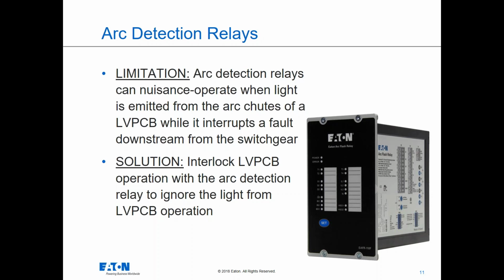The light detection system, while everyone is of the understanding that light detection is faster than a direct electrical method of measurement and then, you know, circling back to a circuit breaker to operate it, what cannot be expressed empirically is what the actual clearing time changes by utilizing these methods. That has to do with tested combinations of equipment. That has to do with light detection sensors being in non-repeatable places within equipment, and the fact that equipment varies from design to design as they're implemented in the field.